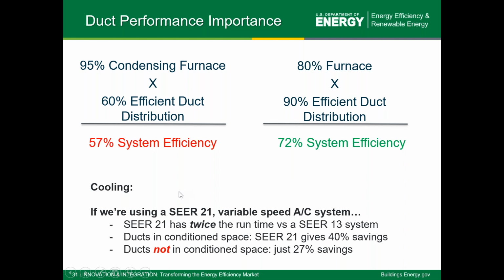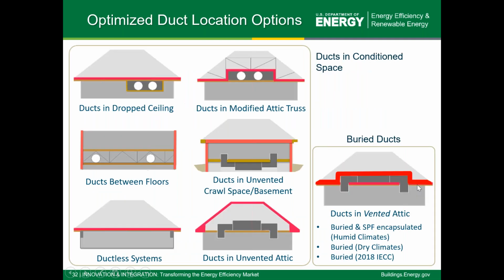Another quick point: we've seen builders invest in very high SEER variable speed cooling equipment, which runs at part load for long periods. If your ductwork is in a hot attic, that long runtime takes its toll, and you get a greatly reduced efficiency benefit from that SEER 21 compared to if the ducts were in conditioned space. So a couple quick points as to why ducts really matter.